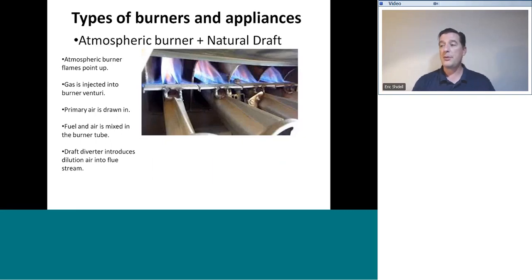Here's a shot of what those burners look like looking into that heat exchanger along the tops of the burners. And here we see the flames. Now, you cannot accurately tune a burner just by looking at it. Ideally, you should be adjusting burners using a combustion analyzer. But that is a bit more outside the scope of this course. That's a bit more advanced. And we do talk about combustion analysis in some other classes. But do be aware that combustion analysis is really required to accurately tune any burner of any fuel source, including gas burners like this one.